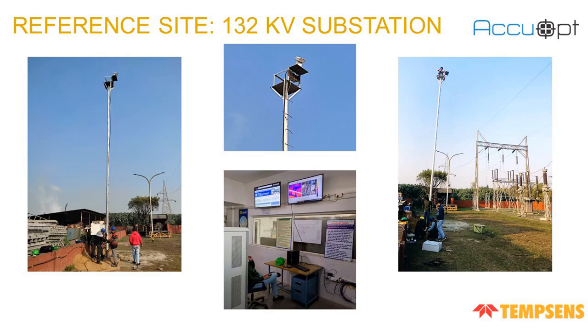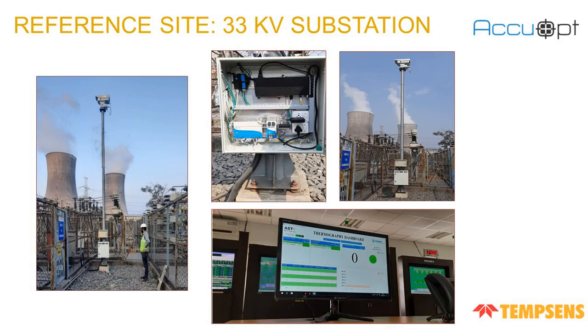In the 132 kV substation, as you can see in the images, we have installed our camera on a pole, which is around 2 to 3 meters higher than the highest component, so that it can cover the complete area and have a clear image, with line of sight between the equipment and camera. Also, this is the reference site of a 33 kV substation. It also has visuals of our junction box, which includes the networking accessories for data configuration and communication between the camera and the PC.